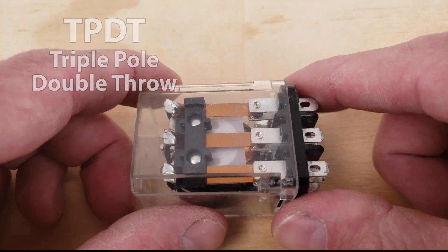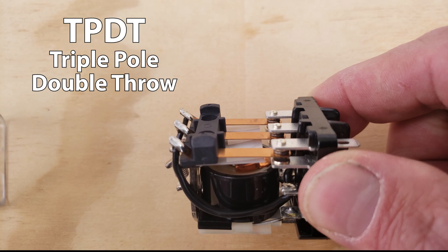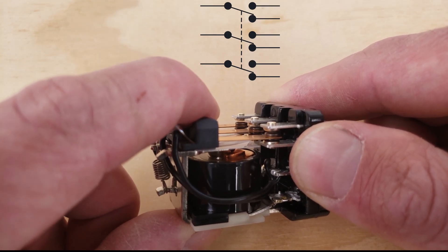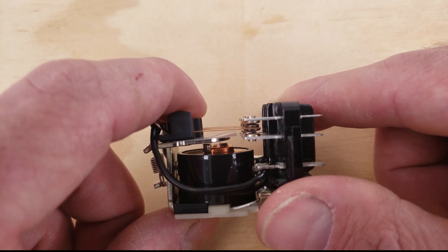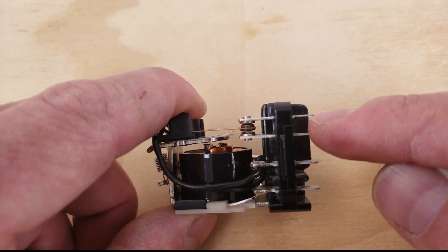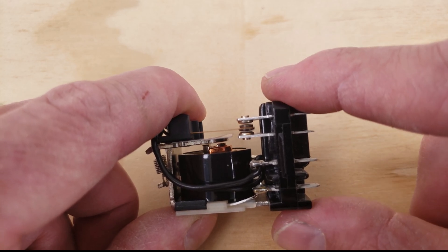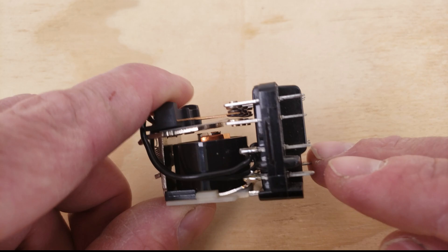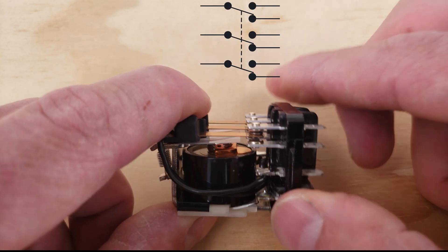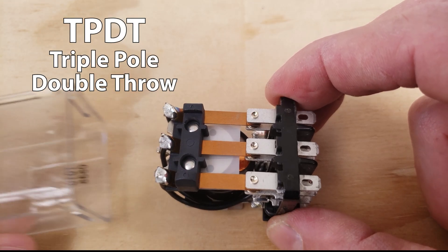Next up you have a triple pole double throw switch. This is an ice cube relay and you can see the three poles or three switches. It's going to have three tabs — your common connection point and then your other two are going to be your two throws. You would power your coil down here in order to get your switch to activate. So that's a TPDT.